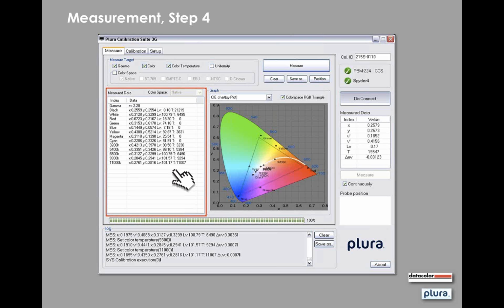If you have another monitor, a third-party monitor, and you want to match it to the Plura monitor, for example, or to any other monitor, you may still use the software to measure, but of course you cannot calibrate automatically because there is no protocol between the third-party monitor and the software. However, you can measure the values, and then you have to go manually adjust the monitor values. Some manufacturers do give you some access, some don't. So this is important for you to know.